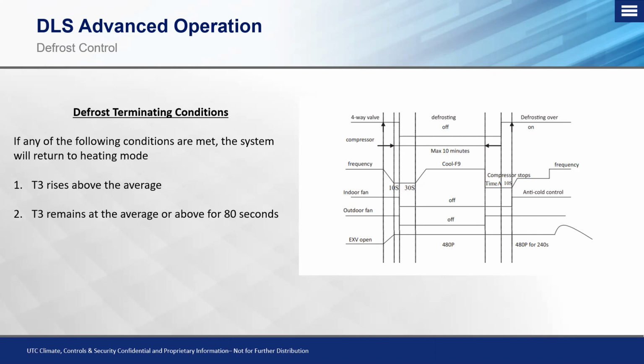Frost is normal on the outdoor coil as it runs, of course, because we need to get that outdoor coil colder than the ambient conditions so that we can absorb heat from the atmosphere and discharge that into the space to properly warm the space as needed, depending on what the set point is. Now, if the outdoor temperature is 25 degrees, well, we know that coil is going to be colder than that, so we're going to build frost. One thing we need to keep in mind is that frost is normal on there.